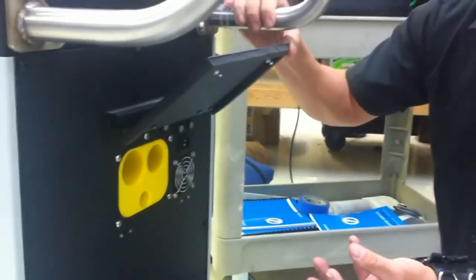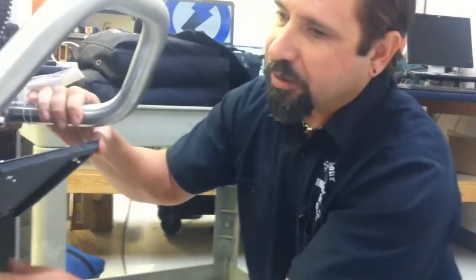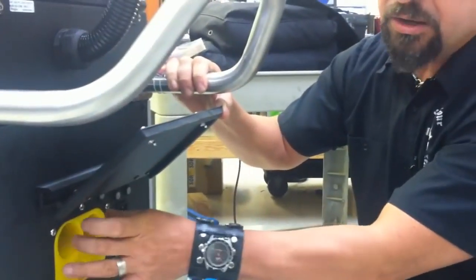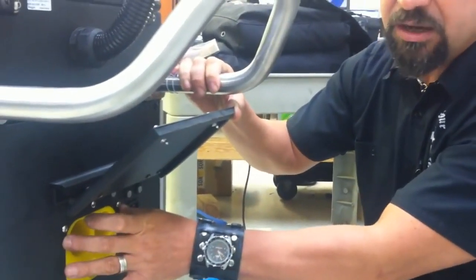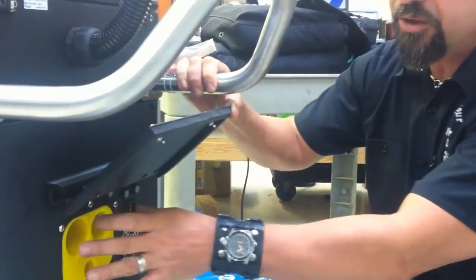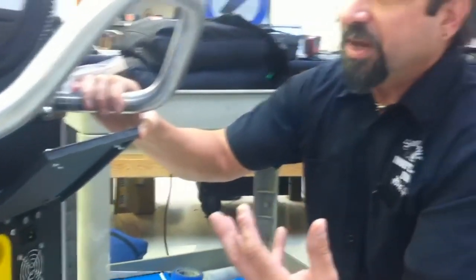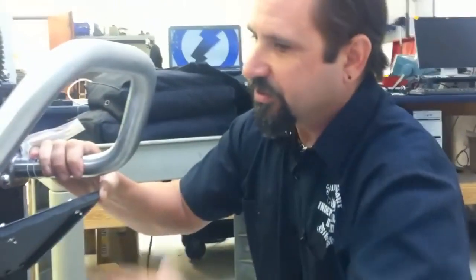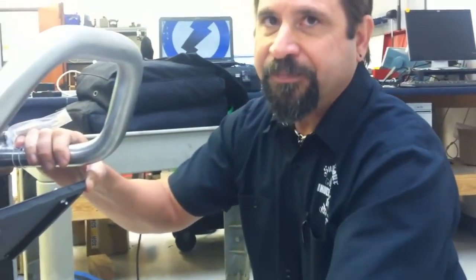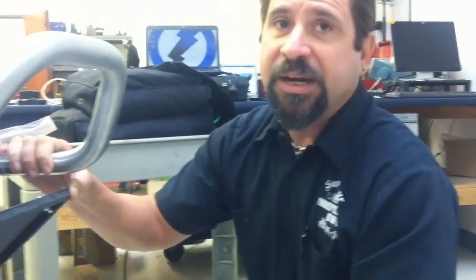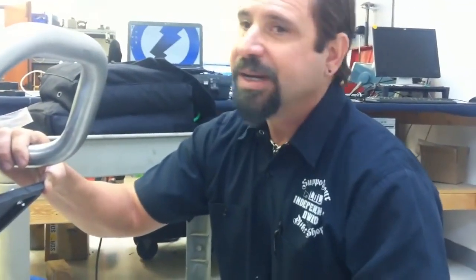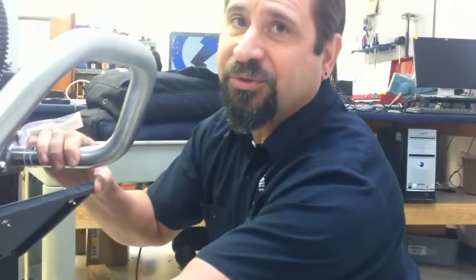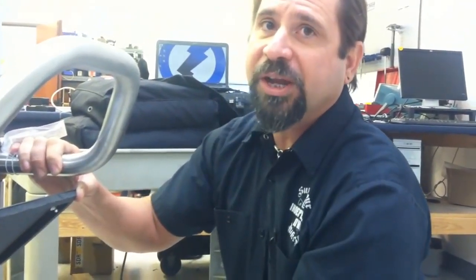In many of the earlier generation thumpers that you'll see on the marketplace, the high voltage cables are permanently attached and terminated within the chassis of the surge generator itself. This basically means that you have coils of cable on the back of the instrument. If damage occurs at any time to your output cables, you're in essence sending a 200-pound unit back to the factory just to have repair done on the cable.